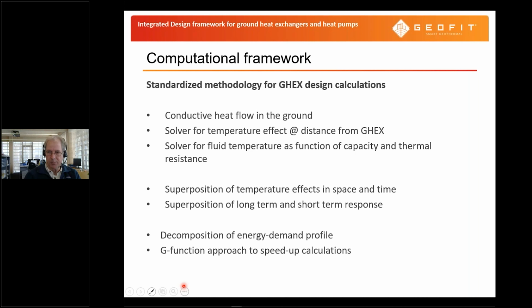So it's a pretty basic approach that's been used in many other engineering tools as well, only we've extended it to all the different ground heat exchangers that we can think of. The main things are superposition of temperature effects in space and time, we'll get to that a bit later, and superposition of long-term and short-term response as well. What is needed for this is also a decomposition of the energy demand profile, because with the superposition methodology and the analytical models that we use, we can only calculate it for a constant energy demand. So we have to use a superposition of different energy steps. And to speed up the calculations, we use a G-function approach.